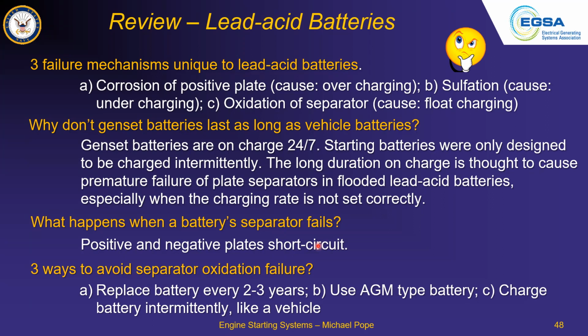Okay, so if you've got a standby generator set and you've got a lead acid battery on it, it's better to schedule a replacement at the most every 3 years, especially if it's a standby generator set. It's better to do that than to risk a failure. So we'd strongly recommend a 3-year replacement maximum. Use an AGM battery, better than the flooded type of battery.